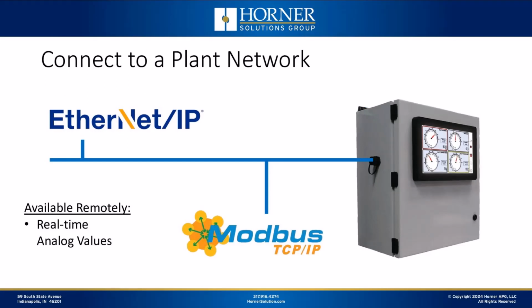Now, in addition to that Ethernet functionality that I just described in terms of pulling and pushing files, there's also the ability to connect the chart recorder to your factory network. Maybe you've got a third-party PLC and an Ethernet IP network somewhere in your plant, and you'd like to get these 4 process analog values on a quick, fast basis into that existing control system. You can very easily do that using Ethernet IP. So this chart recorder is an Ethernet IP I/O adapter. So it's very easy to get those analog values real time into an existing PLC over that protocol.